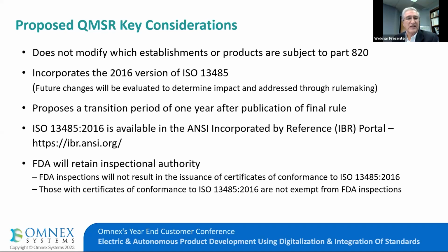Another interesting thing is the FDA will retain their inspectional authority. In other words, FDA inspections, when they come, if they do, will not certify you to conformance or compliance to 13485. However, if you get a certificate to 13485, it does not exempt you from FDA inspections. We'll always have FDA inspections for cause. They can drop by anytime, any place, or, of course, for your convenience.